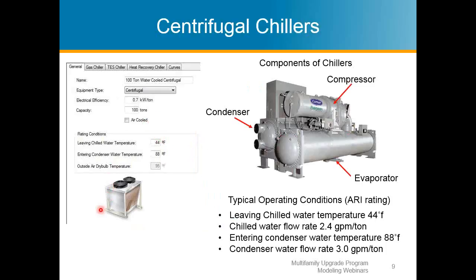On the screen on the left is basically a screenshot of EnergyPro, and the image on the right is just a basic chiller that we have in here. And there are 3 components to it. You have your evaporator, which is going into your indoor unit. Then you have the condenser side, which is taking it to the cooling tower, typically located outside or on a roof, and then you have your compressor.